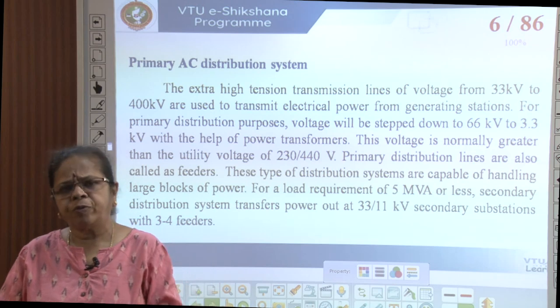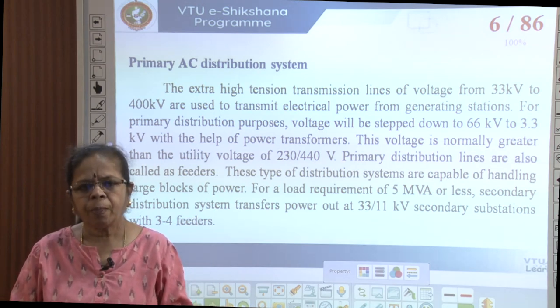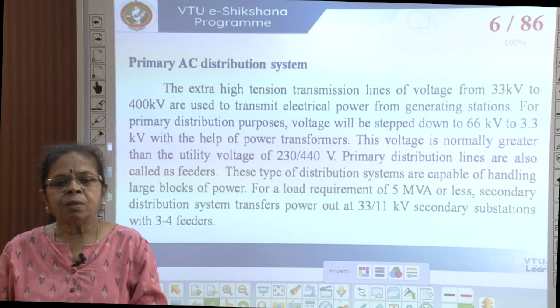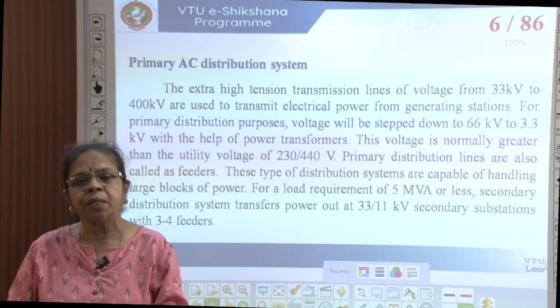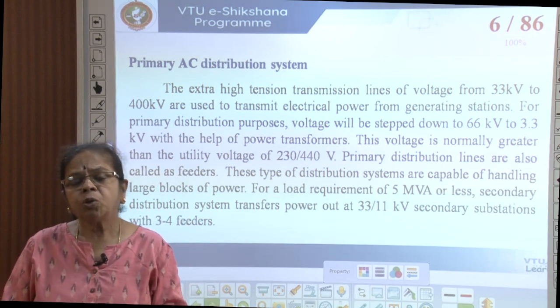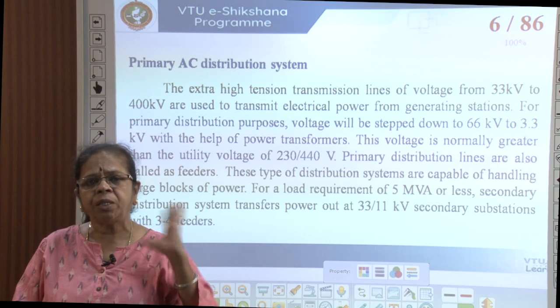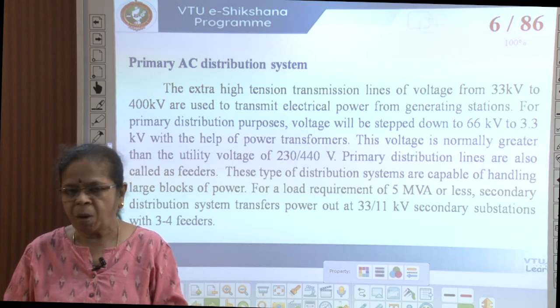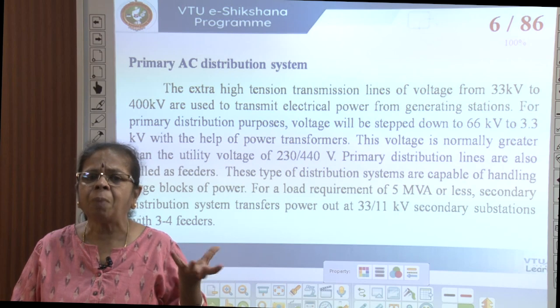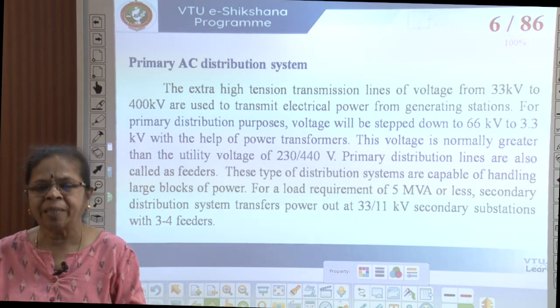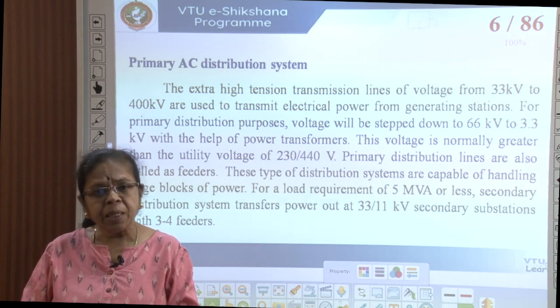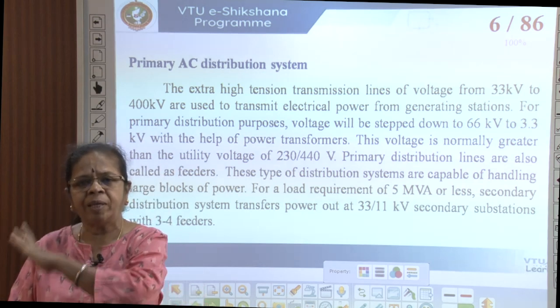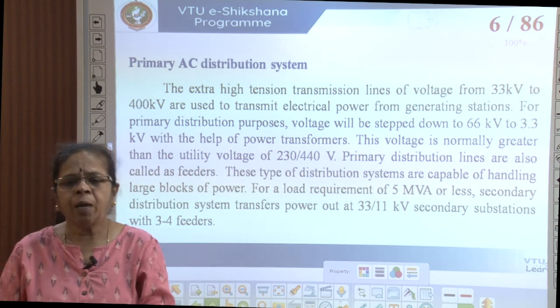These are the various ways of classifying distribution systems. We also have primary and secondary distribution. Higher transmission voltages from 33 kV to 400 kV or above are used to transmit power from generating stations to substations. Normally 400 kV and above is commonly used; 33 kV is used when generating plants are small and closer to the load center. For primary distribution, these voltages are stepped down to 66, 33, 22, 11, 6.6, or 3.3 kV with the help of power transformers.